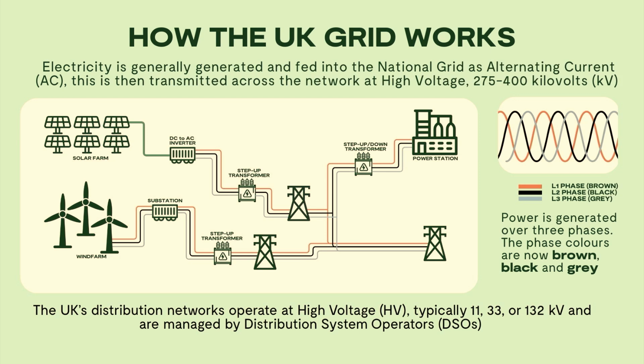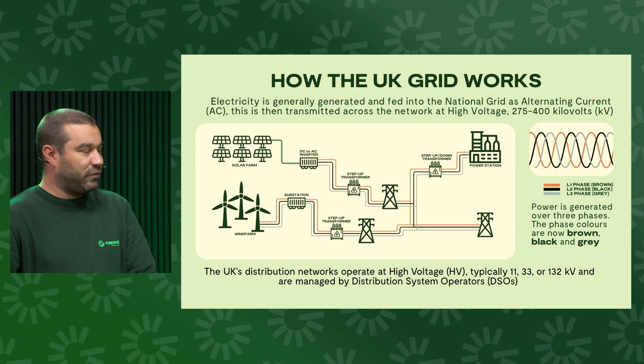Downstream from the transmission network are the distribution system operators, or distribution networks, running at medium voltage, around 11 kV or 33 kV. We step down in a cascade from high voltage transmission to medium voltage, and ultimately to low voltage, typically 400 volts three-phase or 230 volts single-phase, because that's the level needed to power physical equipment.